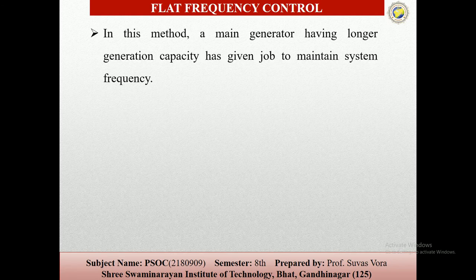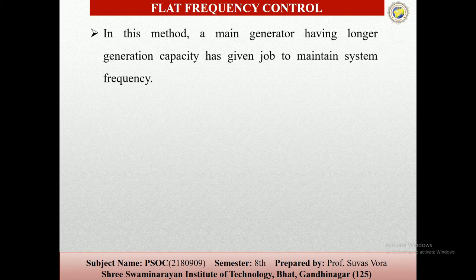So the flat frequency control system is nothing but connecting two systems in parallel. In this method, the major generator, having the larger generator capacity, has the job of maintaining the system frequency.